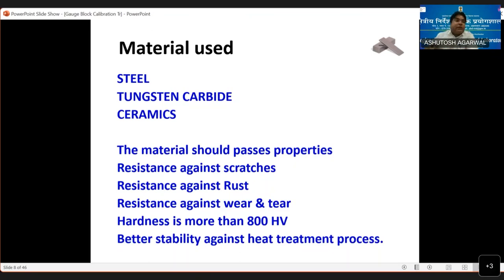Those industries which cannot afford ceramic need resistance against rust. There should not be rust. Ceramic has no rust, tungsten carbide has no rust, but steel has some rust. But steel is mostly used because it's cheaper and scratch resistant. Hard strength, then strength against wear and tear, and hardness should be more than 800 HV to make the gauge block. There should also be better stability against the heat treatment process. When temperature is increased, it should not shrink or contract so much that it cannot maintain its dimension.